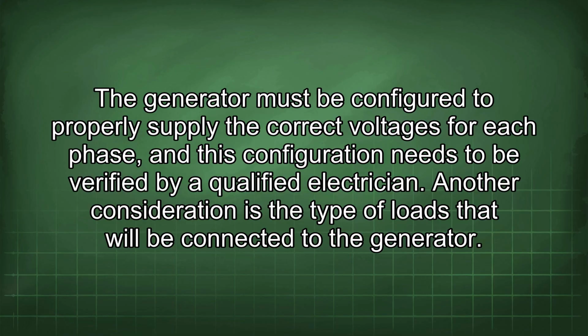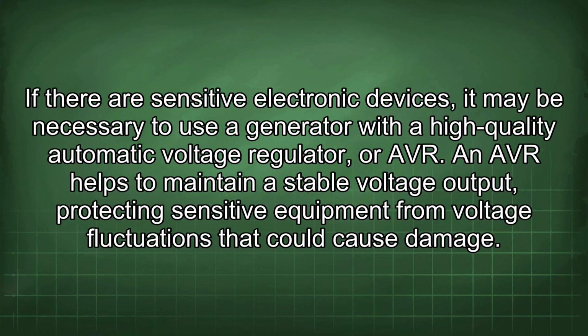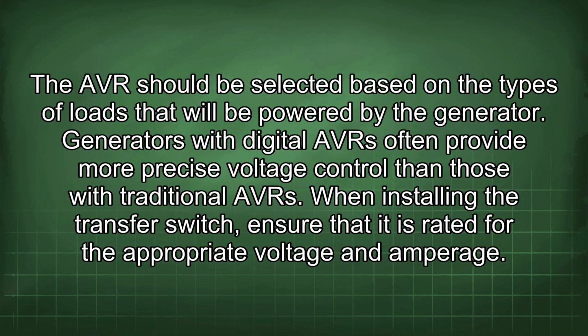Another consideration is the type of loads that will be connected to the generator. If there are sensitive electronic devices, it may be necessary to use a generator with a high-quality automatic voltage regulator, or AVR. An AVR helps to maintain a stable voltage output, protecting sensitive equipment from voltage fluctuations that could cause damage. The AVR should be selected based on the types of loads that will be powered by the generator. Generators with digital AVR often provide more precise voltage control than those with traditional AVR.